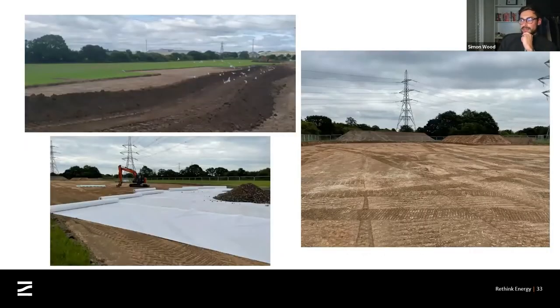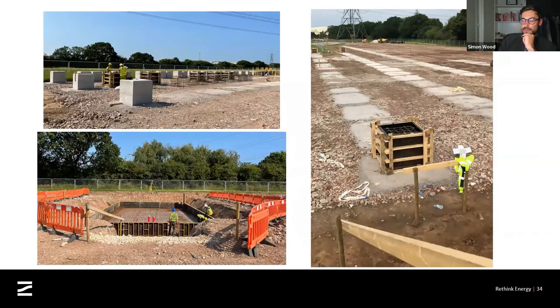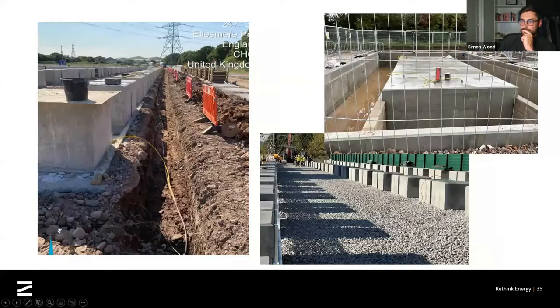The next few slides just give you a timeline of events of how we've gone from a field, essentially, to the site that I just showed you. A lot of civils works to begin with, early groundworks to level the site, and then formation of all of the foundations required, both for the battery containers, the MV skids, switchgear, control rooms, and so on, and the supergrid transformer. And you can see the sense of scale there, just as to how significant that foundation needs to be for the size of that transformer.